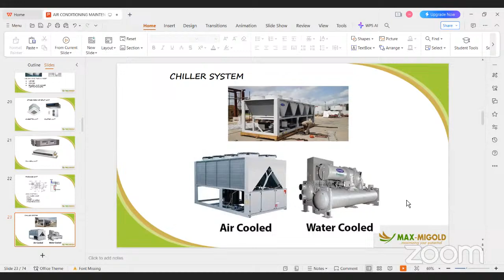Then there's another type they call the absorption chiller. The absorption chiller is another form of AC that does not use those 4 basic principles that I've mentioned. They use heat actually, and convert that heat passing through there into cooling. The refrigerant they use for this particular system is called lithium bromide.